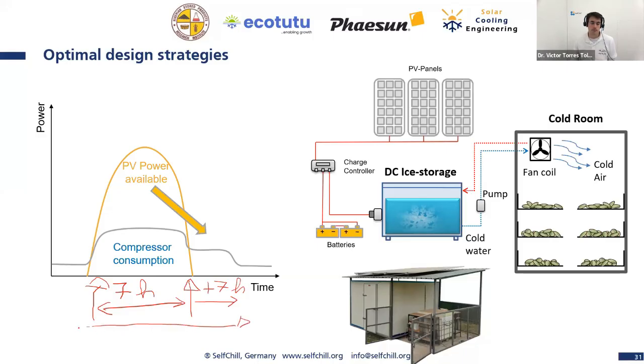And during this time, they are producing ice. 16 hours per day, they are producing ice from the solar during the day from the PV panels, during night from the small batteries. Then we have a water pump and a heat exchanger that is pumping the cold water in the heat exchanger, and with the fan is producing cold air. So you see here, getting the cold air, the cold water.